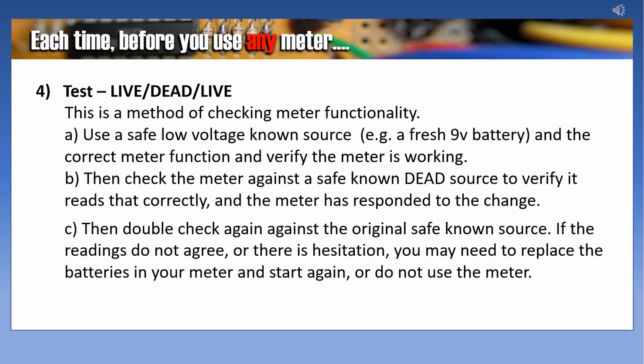The 4th daily habit is to test live, dead, live. This is a method of checking meter functionality. To begin with, you use a safe low voltage known source, such as a fresh 9-volt battery, and check the correct meter function and verify the meter is working. Then, check the meter against a safe known dead source to verify it reads that correctly and the meter has responded to the change. And finally, double check again against the original safe known source. If the readings do not agree, or there is hesitation, you may need to replace the batteries in your meter and start again, or do not use or trust the meter.